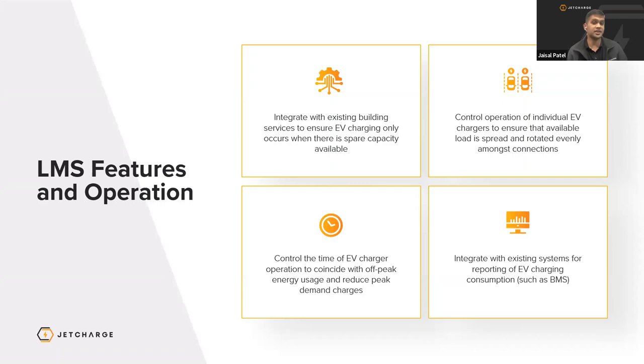The third feature is that they control the time of EV charger operation to coincide with off-peak energy usage and reduce peak demand charges, so scheduled charging. And the fourth feature is essentially they would integrate with the existing systems for reporting of EV charging consumption, such as a BMS. Now, not all load management systems do all of these things, but almost all load management systems do at least one of these things to ensure that we do not exceed the site's capacity for EV charging. Next slide.